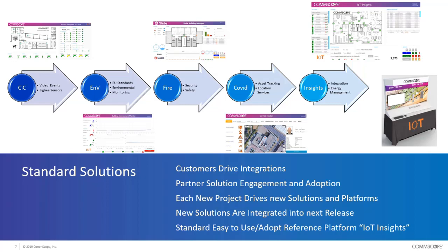Another project looked at door contact sensors and fire doors. We can detect that somebody opened a fire door — that's not a problem — but if that fire door has been left open for one minute, three minutes, five minutes, or ten minutes, we can set an alarm and send a notification to the facilities team to go close that fire door, because it is a risk and there might be a citation. We can also detect if somebody has been tampering with sensors on doors and proactively investigate that device.